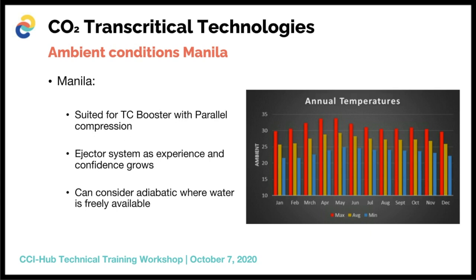As we are comparing these technologies to ambient conditions, I had a bit of a look at what can be seen within the Philippine regions. So I've included a graph showing the high ambient temperatures over each month for a year period, then the minimum average temperatures, and then the daily average temperatures that can be seen in Manila. From this, as I've mentioned before, you can see that the Philippines has quite a constant ambient temperature, which from a design point of view makes it really suitable to design systems for the Philippines, as you do not have a very wide range in operating conditions.